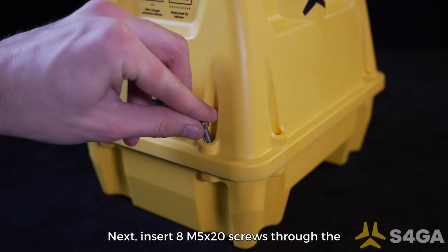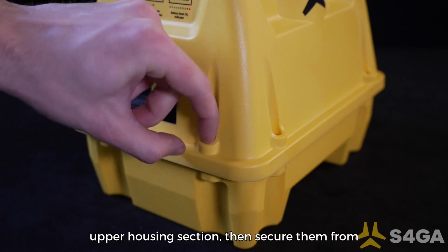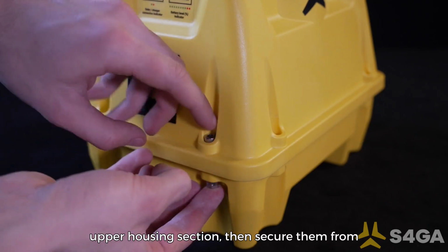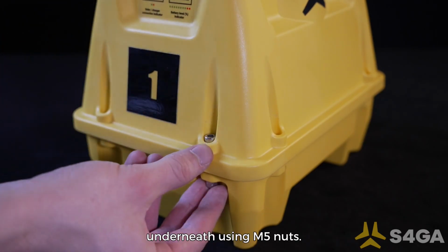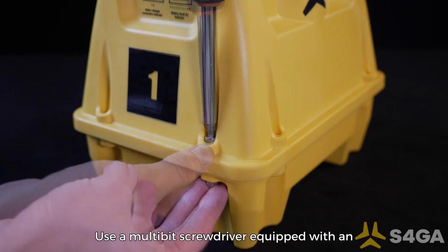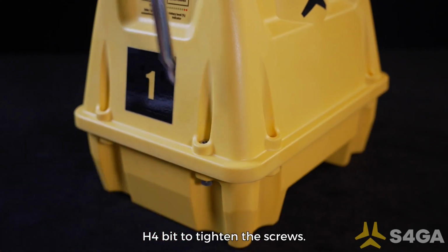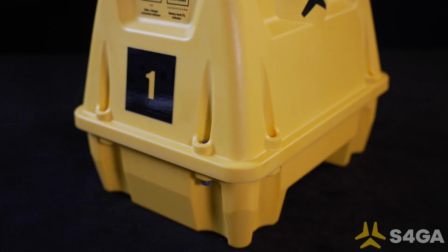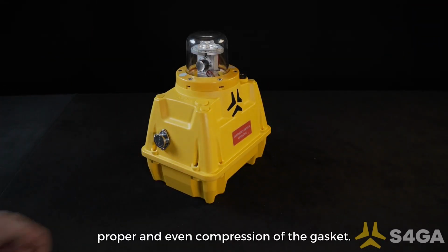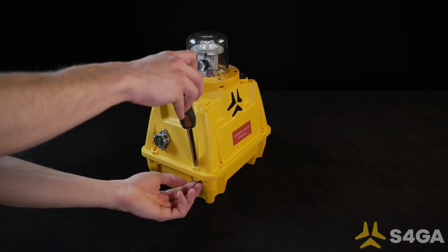Next, insert 8 M5x20 screws through the upper housing section, then secure them from underneath using M5 nuts. Use a multi-bit screwdriver equipped with an H4 bit to tighten the screws. Tighten the screws in an opposite sequence to ensure proper and even compression of the gasket.